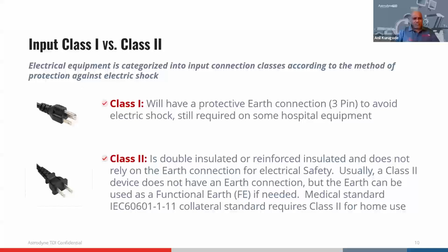This is one of the most fundamental distinctions and naturally brings up a question: if that's so good and safe, why even have another class without the earth? Isn't that a high risk? Yes, it is no doubt a higher risk, but the design procedures are also different - there are more rigorous requirements in terms of isolation, insulation, leakage current, etc. So the most important definition is Class I and Class II at a high level, and that separates the two types of equipment in terms of defining, specifying, and qualifying.